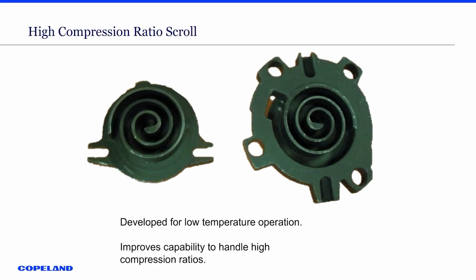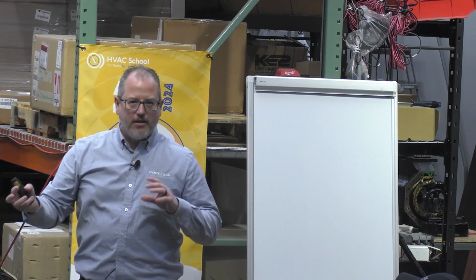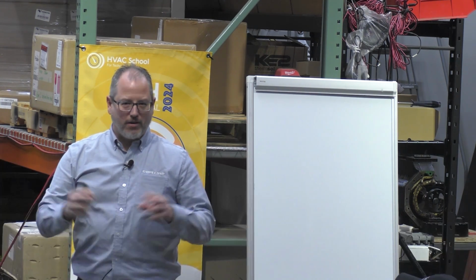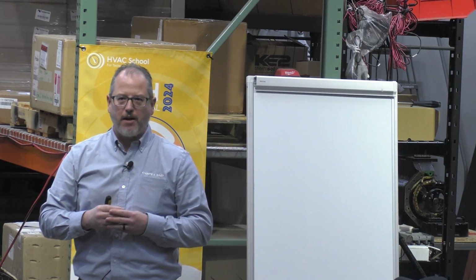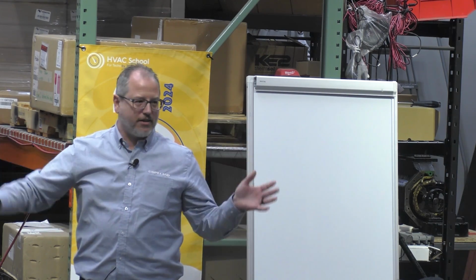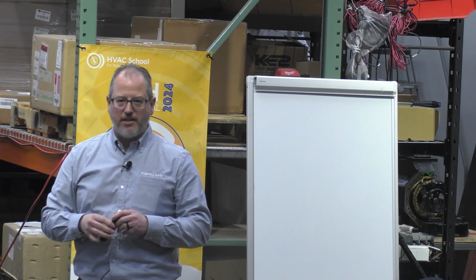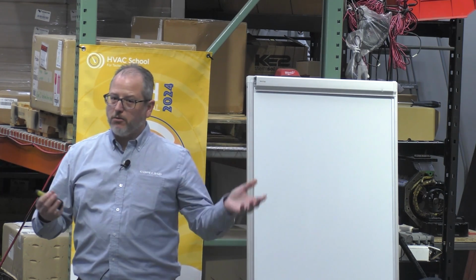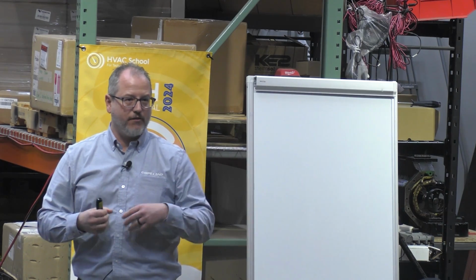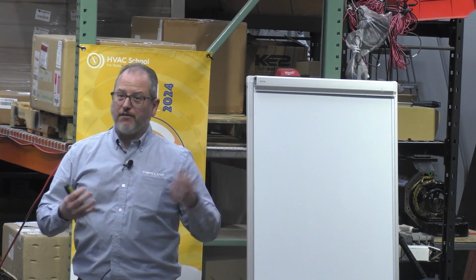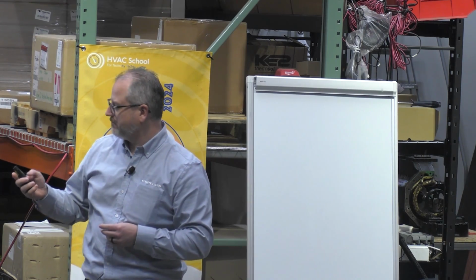So here's a picture of the refrigeration scroll. You see how the lobes at the end are different than the other one? And then it's a little wider. So I just wanted to put that picture in there because if people have not taken compressors apart, which I highly recommend, if you have a problem with a compressor, whatever kind of compressor it is, if it's out of warranty, take it apart. Find out what happened so the next one doesn't go bad. If it's in warranty, see if it has to go back first, okay? And it depends on what kind of compressor it is, but.